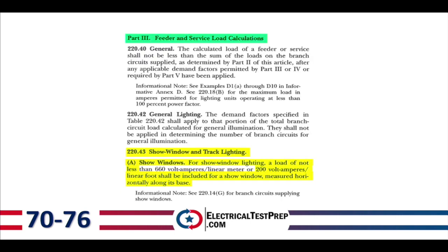Under Part 3, Feeder and Service Load Calculations, section 220.43, Show Window and Track Lighting. For show window lighting, a load of not less than 200 volt-amps per linear foot shall be included, measured horizontally along its base. We already learned that — it's restated here in the calculations section.